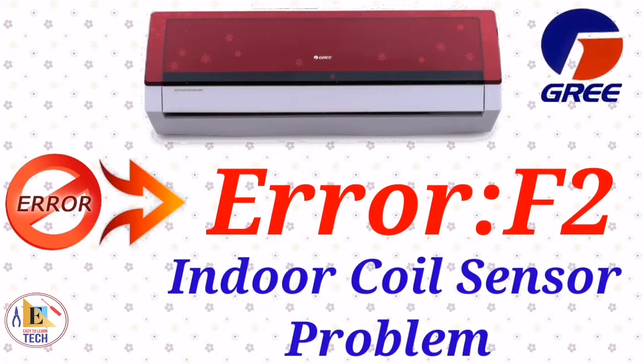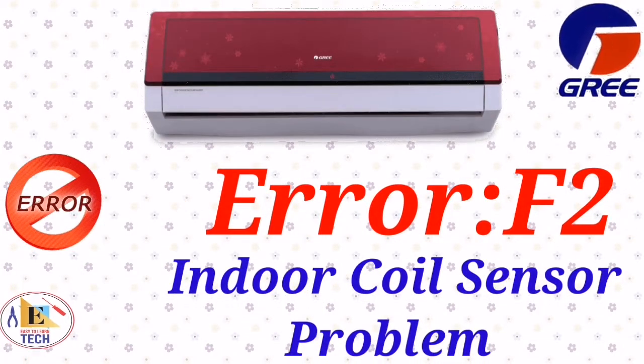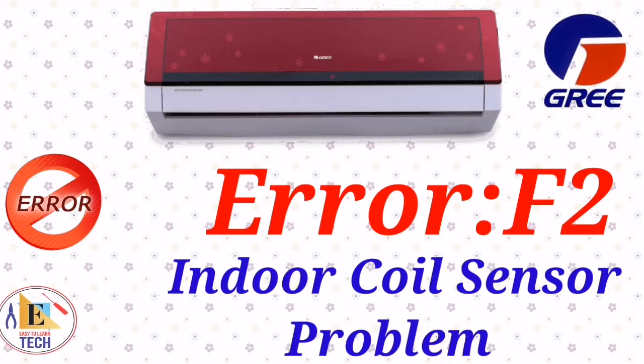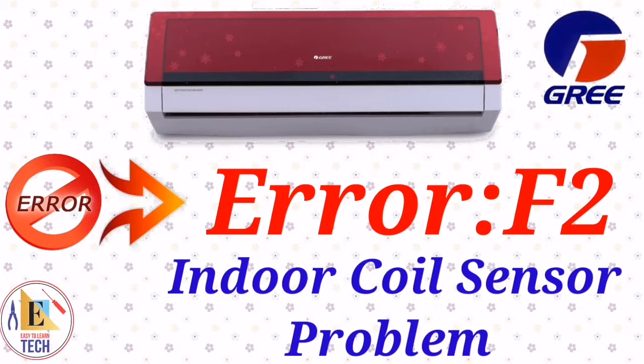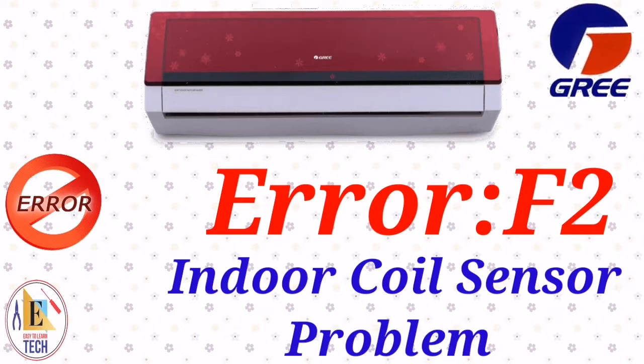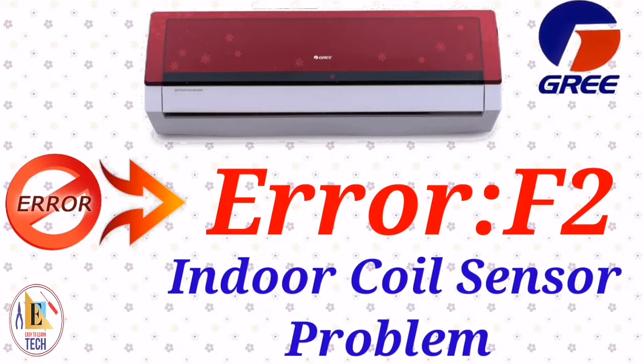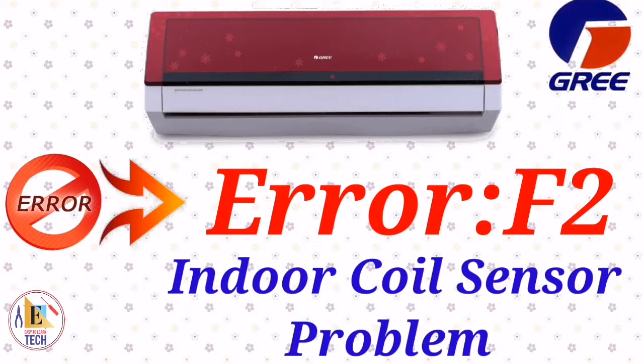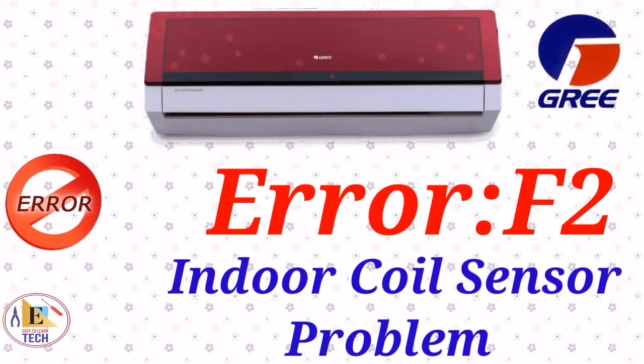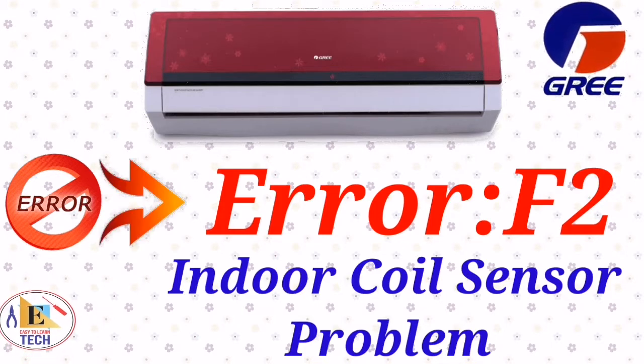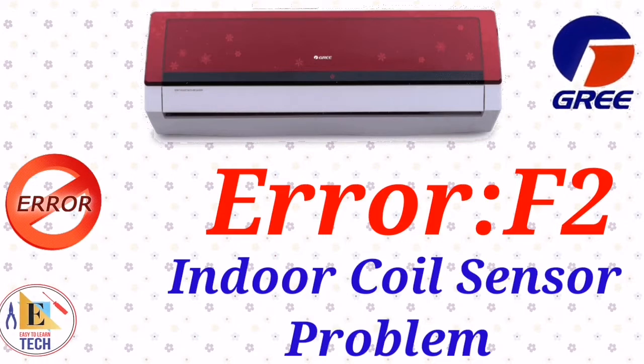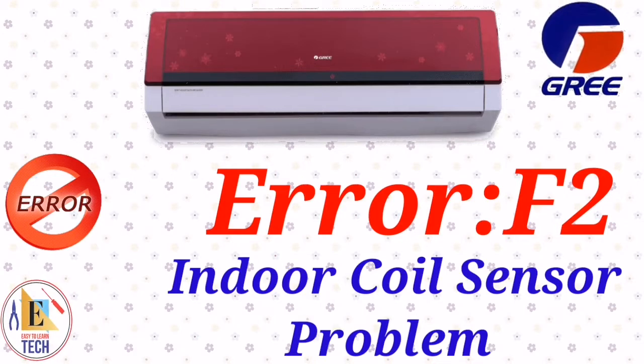When you see F2 in your display, it means indoor coil sensor problem. The indoor coil sensor is installed in our evaporator coil just near the PCB. First of all, you have to check the placement of our indoor coil sensor. If the placement is good, then you have to check the connection which is connected to our PCB. If the connection is not good, then connect it properly and start the unit. And again, if you get the same error, then you have to check the resistance of our indoor coil sensor.